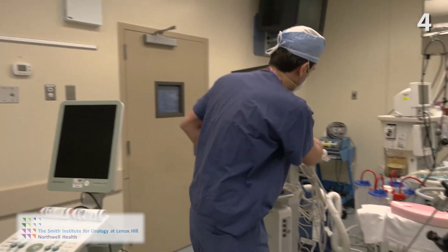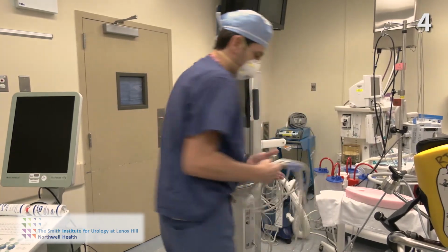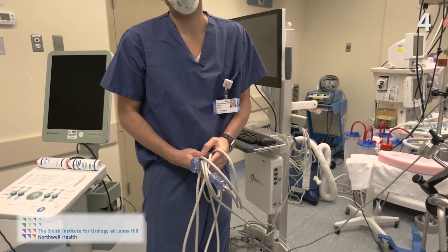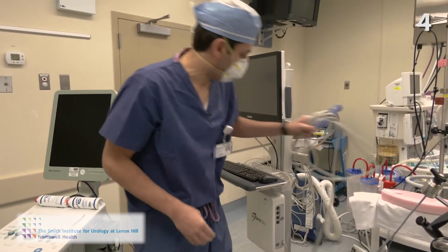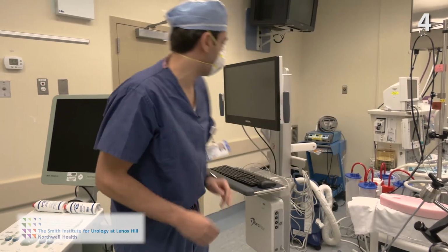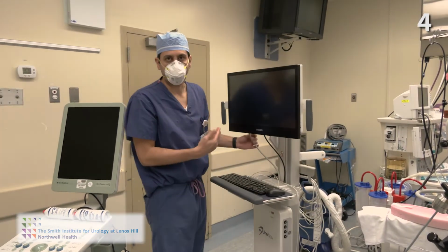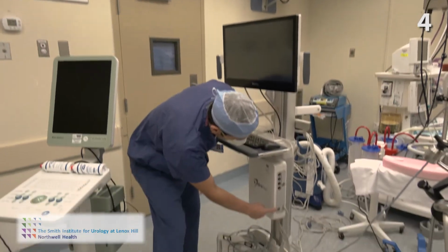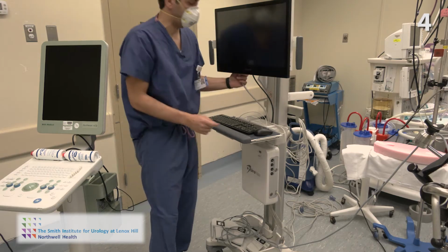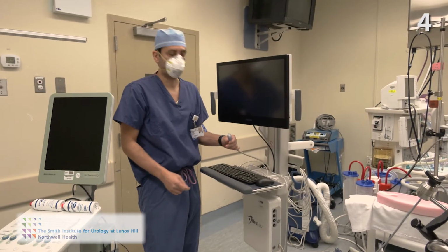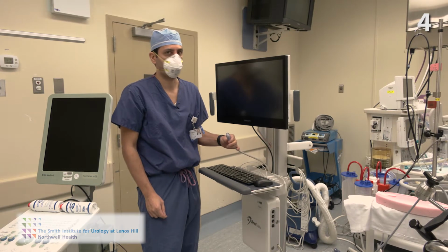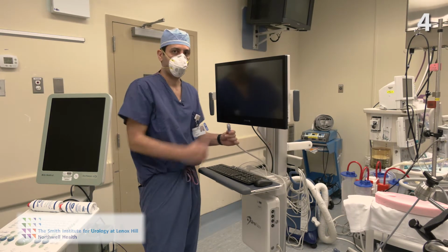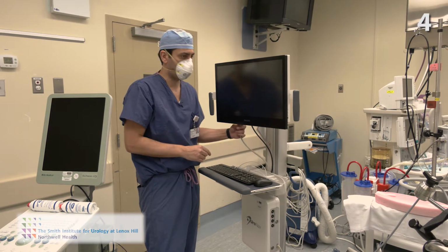The first thing to understand is that the UroNav device has two sets of power plugs. These need to be plugged in, okay? Now, a common problem is after you plug it in, the monitor doesn't come on after you hit the power button right here. The reason is this cable is typically loose, and in this case it's actually out during the demonstration to show you how common it is. When you rotate the screen, this gets yanked out and it won't turn on.